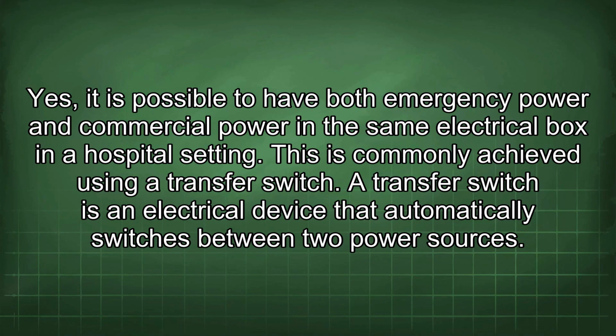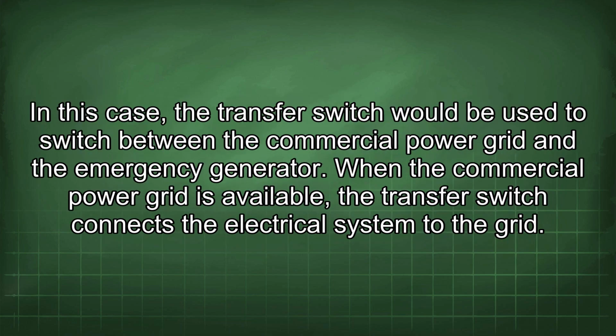Yes, it is possible to have both emergency power and commercial power in the same electrical box in a hospital setting. This is commonly achieved using a transfer switch. A transfer switch is an electrical device that automatically switches between two power sources. In this case, the transfer switch would be used to switch between the commercial power grid and the emergency generator.